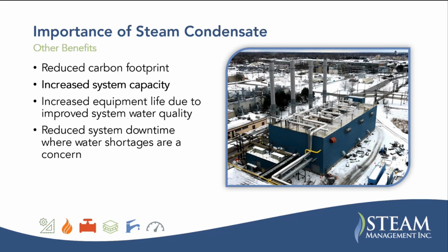Other benefits, reduced carbon footprint. Obviously, that always comes with energy savings. Another big one people don't think about is increased system capacity. There's a lot of plants that are out of capacity, and that's limiting their production. But if they are able to save energy required in their deaerator due to having to heat that makeup water, that gives them available capacity.